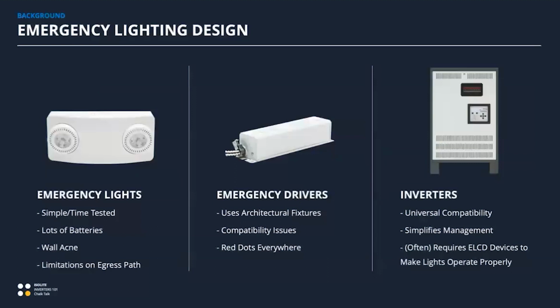And maybe the biggest issue, the one we're going to spend our time on today, is these are batteries-everywhere solutions. When you have a battery in a life safety system, that means maintenance. Every place where there's a battery has to be maintained on a monthly basis. Every month, someone has to go prove that everything is still connected, the battery is still there, and the system still operates.